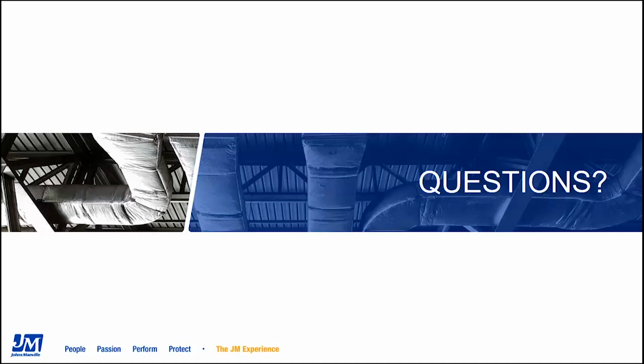Now, the installed R value is basically once you take that fiberglass and wrap it around a piece of sheet metal duct, you're going to naturally compress that fiberglass, and you test that at 25% compression of the out-of-package R value. So if you're a 3-inch duct product, you actually test the thermals at a 3/4 pound product, as that product has been compressed 25%. Think about wrapping around that duct, around those squares, on those corners. As it compresses, you reduce your thermals, because fiberglass traps air. That's how it slows the heat flow and gives you your thermals. But as that product is applied, that's how you get your installed R value. That's how it's tested at 25% compression, and that's the difference.